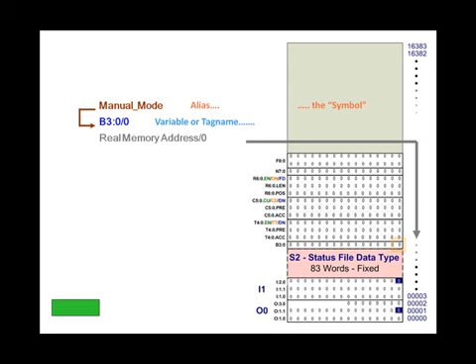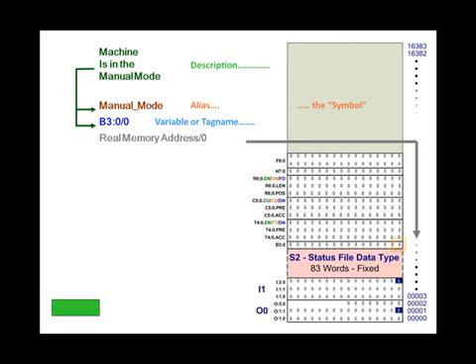The symbol and the variable name are interchangeable. When creating logic, you can type in the symbol and it will bring the base variable with it. With this programming software, the symbol is limited to a single line of 20 characters. If more descriptive nomenclature is needed, the software allows you to add a description and associate it with a variable — limited to five lines of 20 characters. The programming software will not inhibit you from assigning the same description to two separate variables, so beware — it's not like the symbol, where it prevents you from using the same symbol twice.